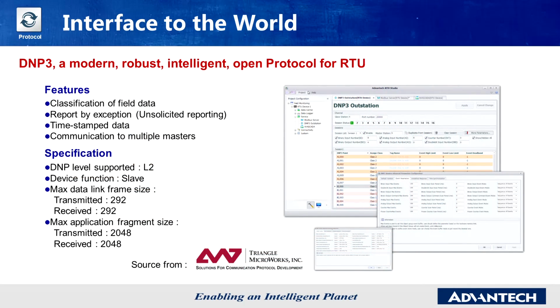DNP3 is a very modern and robust intelligent protocol, especially for RTU applications. It features classification of field data, and it also supports report-by-exception functions, timestamping, as well as communication to multi-masters. One thing worth mentioning is that the source code comes from the very famous provider Triangle Microworks, so the DNP3 in the RTU is well certified.